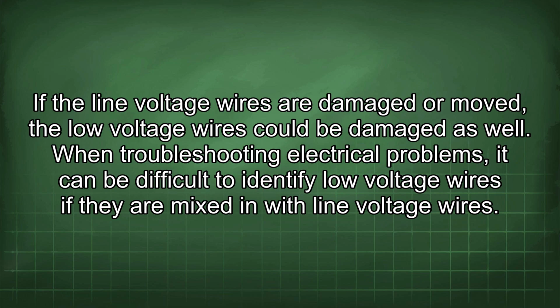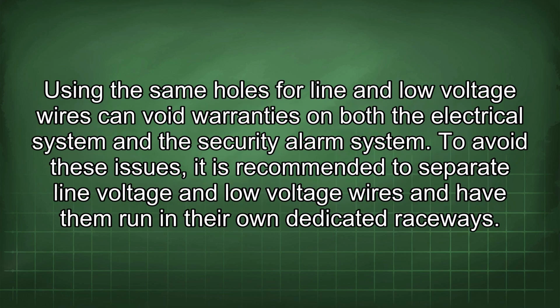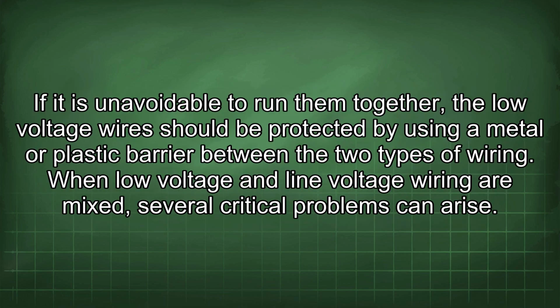When troubleshooting electrical problems, it can be difficult to identify low voltage wires if they are mixed in with line voltage wires. Using the same holes for line and low voltage wires can void warranties on both the electrical system and the security alarm system. To avoid these issues, it is recommended to separate line voltage and low voltage wires and have them run in their own dedicated raceways. If it is unavoidable to run them together, the low voltage wires should be protected by using a metal or plastic barrier between the two types of wiring.